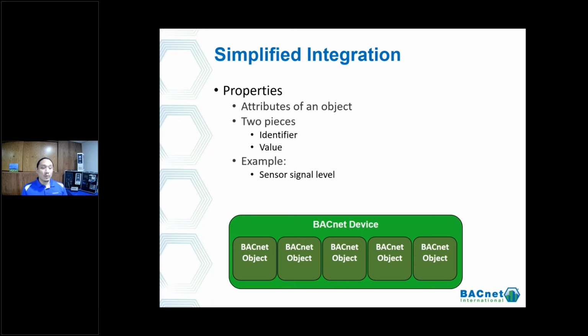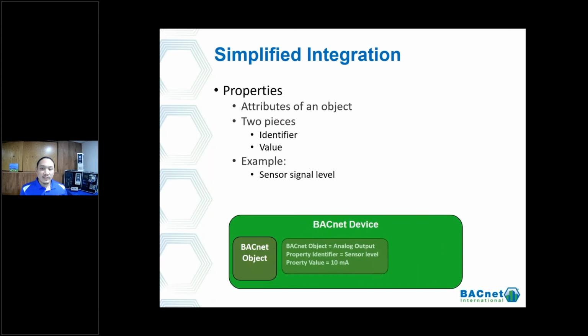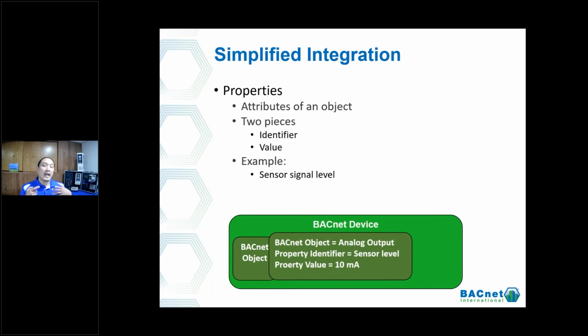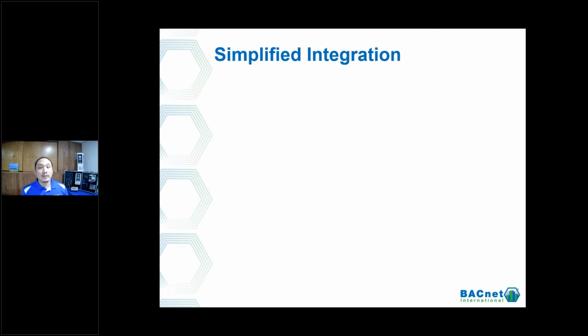One example: a sensor signal level, say a pressure transducer inside your duct. I want to read this information, so I read an analog output object, looking down the list for my sensor level. I found it, and it's coming back with a value of 10 milliamps, telling me that's the value present for this sensor. Now you're breaking down to the information you're looking for.